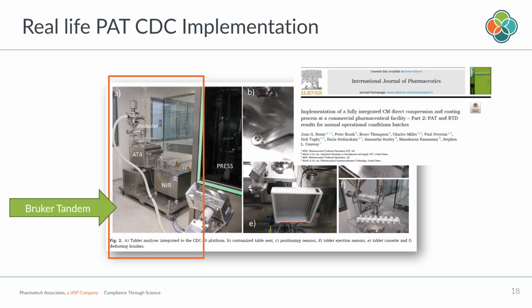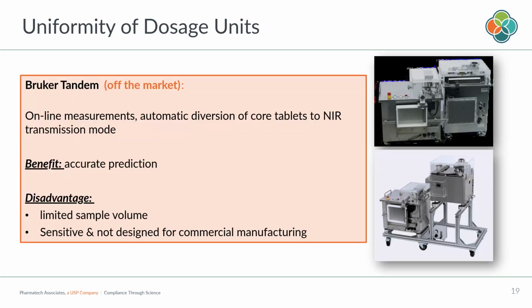You can see it on this picture, a bit better on the next picture, which was a combination of a typical inline tablet inspection system, weight, hardness, thickness measurement device, plus a backpack, basically a Bruker MPA transmission NIR to measure the content uniformity of each of the tablets, which have been weighed on the real tablet weight. This was a design of the earlier days, sold a couple of times, but it was taken off the market from the company Bruker because of a couple of issues.